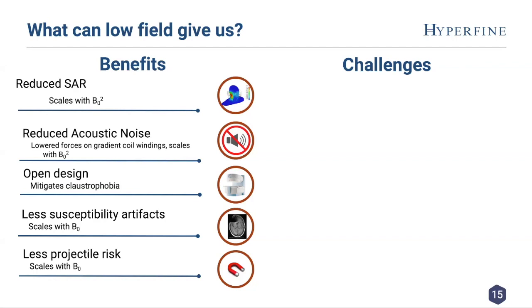The susceptibility artifacts go down with B-naught. This is actually a double-edged sword because we have fewer artifacts, but we also have less sensitivity to susceptibility effects like T2 star susceptibility when imaging, that category of scanning. So the effects are still there, they just take longer to evolve. And for safety, the risk of projectiles is much lower; that also scales with B-naught.